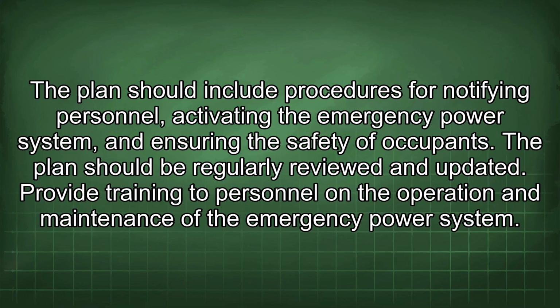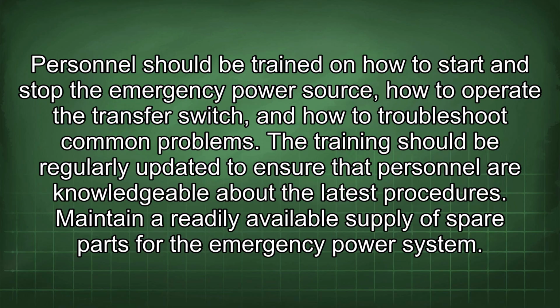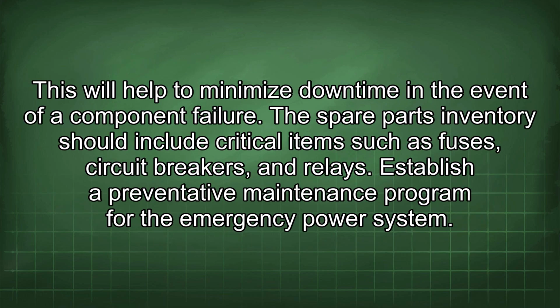Provide training to personnel on the operation and maintenance of the emergency power system. Personnel should be trained on how to start and stop the emergency power source, how to operate the transfer switch, and how to troubleshoot common problems. The training should be regularly updated to ensure that personnel are knowledgeable about the latest procedures. Maintain a readily available supply of spare parts for the emergency power system. This will help to minimize downtime in the event of a component failure. The spare parts inventory should include critical items such as fuses, circuit breakers, and relays.